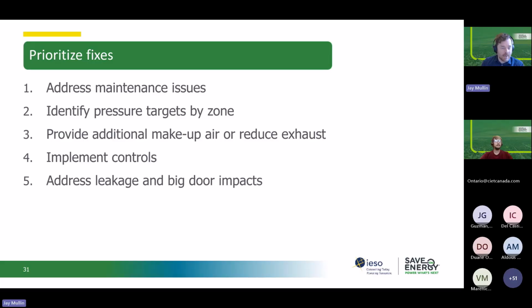Because if your exhaust is truly higher than your outdoor air supply is capable of meeting, there's a couple of levers that you can use. This is a really common situation where there's a lot more exhaust happening than makeup air units supplying air. You can add more outdoor air supply: add more makeup air units, increase outdoor air percentage. You can reduce your exhaust if this is allowable by your processes, things like shutting down exhaust when not needed, installing demand control VFDs on the exhaust units. To help balance some of the energy considerations, you can add heat recovery or smarter scheduling to minimize the energy impact of high air changeovers.